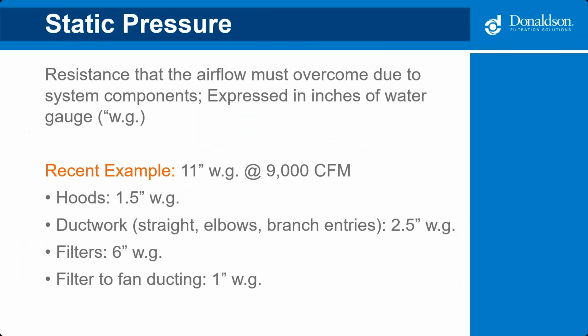So here's an example from a recent system that we designed. The hoods totaled 1.5 inches water gauge. We'll just say inches from here on out. The ductwork, including straight runs of duct, elbows, and branch entries, totaled 2.5 inches. The filters and the collectors totaled 6 inches. The filter to the fan ducting was 1 inch. So the total system static pressure, if you add that up for this particular project, was 11 inches.